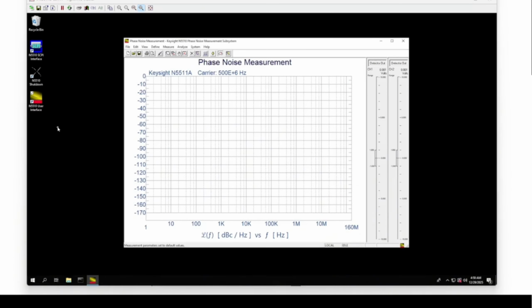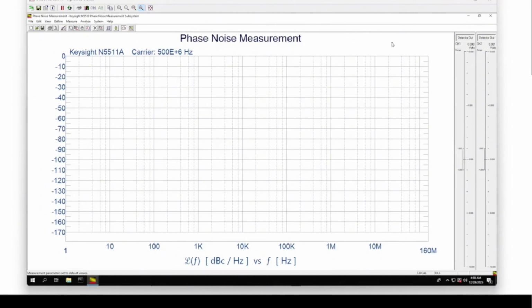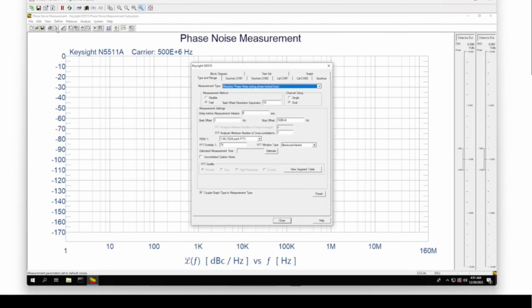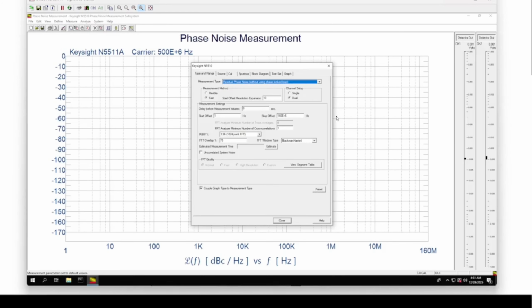So when you first turn on the N5511A phase noise test system, this may not be booted up. So just double click on the user interface here and you'll be prompted with the screen. Let's see if I can maximize this so that's a little clearer. So the first thing you would want to do is to define, click on measurements. We're not running absolute phase noise, we're running residual phase noise measurements. So let's click on that.